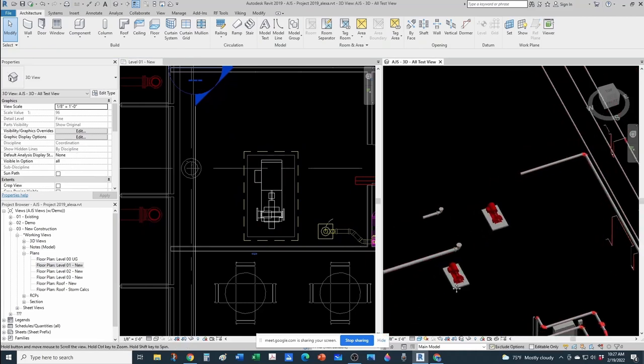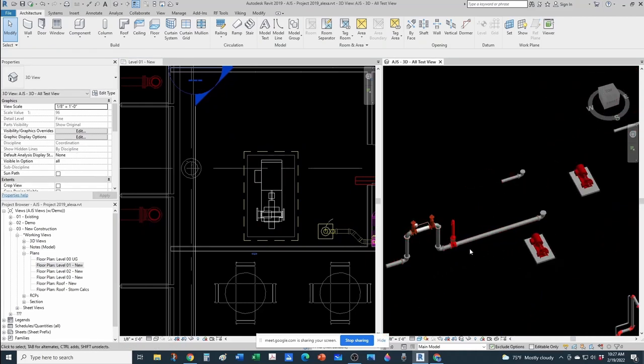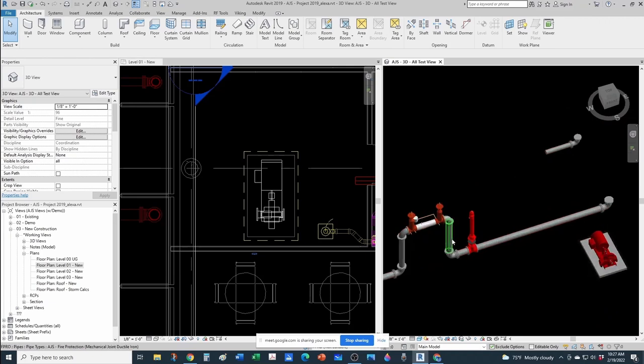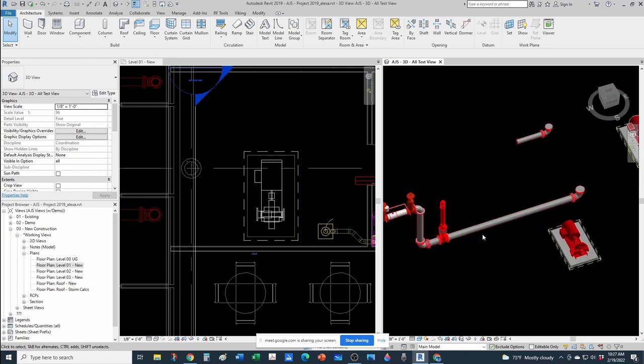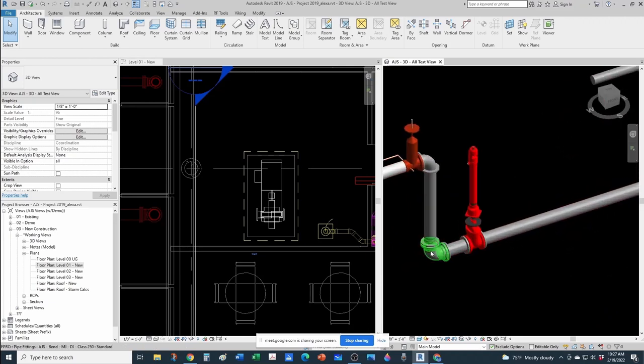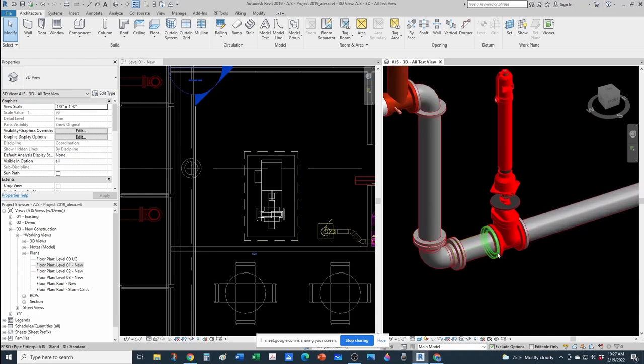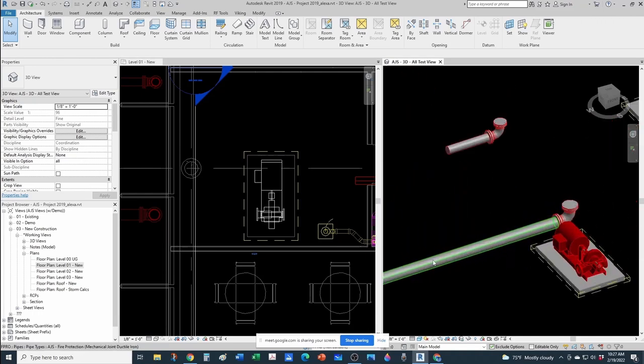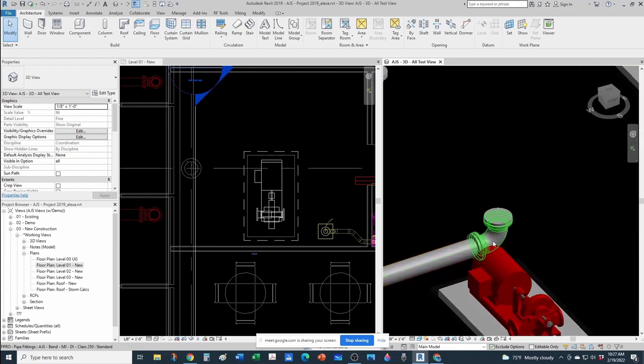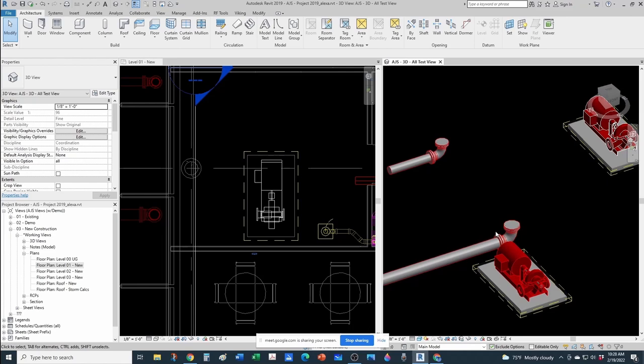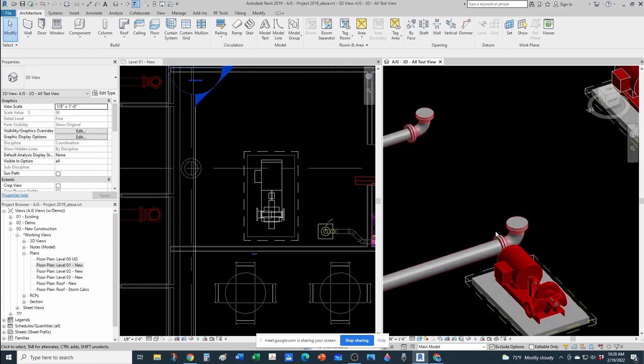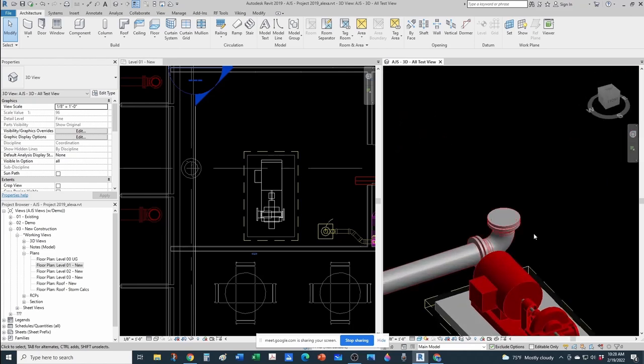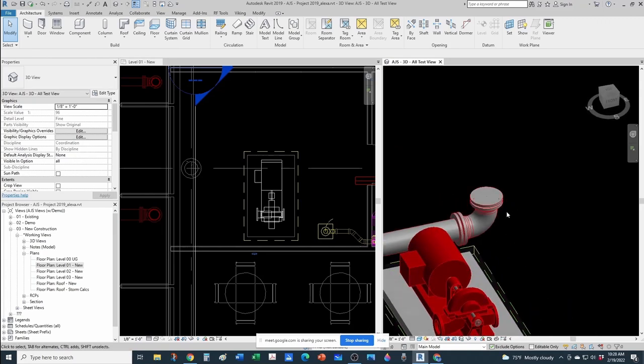Now let's go with our piping, right? We're not going to replicate this part because that's not part of the fire pump room itself. But again, this would be mechanical joint, which would have some restraints. Whenever you have an inrush of water flow, this elbow is going to try to separate. So many times they will use some mechanical restraints there, or a thrust block here, which is just a piece of concrete here to avoid this elbow separating from the piping.